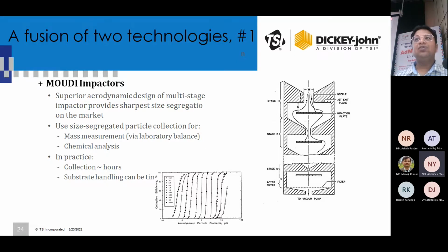So no matter when you are using it, it's always the change in frequency, not the calibration. So virtually this instrument is calibration free. If some parts get broken or something, you just take it and put it there. It's done. You don't need to calibrate, because the quartz crystal has its own properties which will never change. So that's why we have it as a standard product, because it's based on quartz crystal. It is one step ahead. Plus, there is one more thing: usually you measure only either PM 2.5 or PM 10.